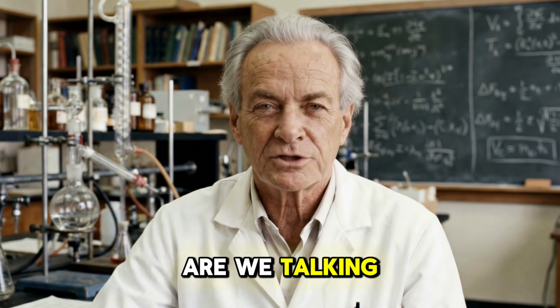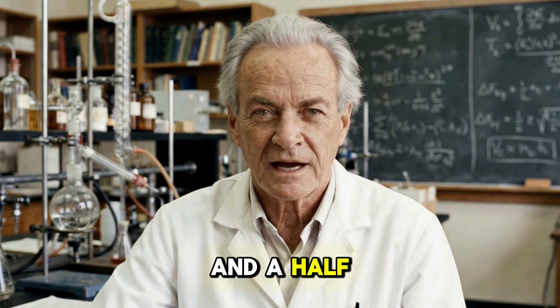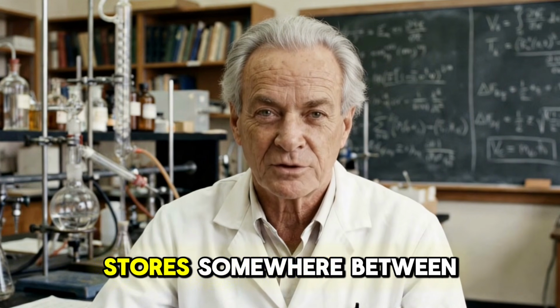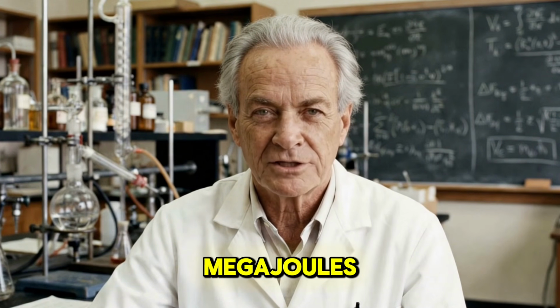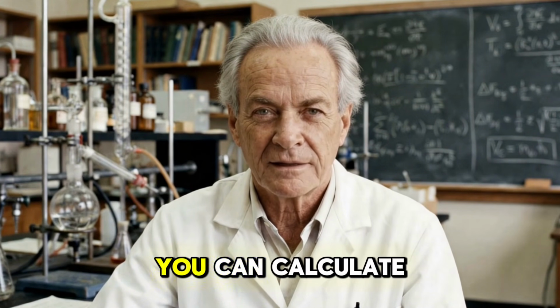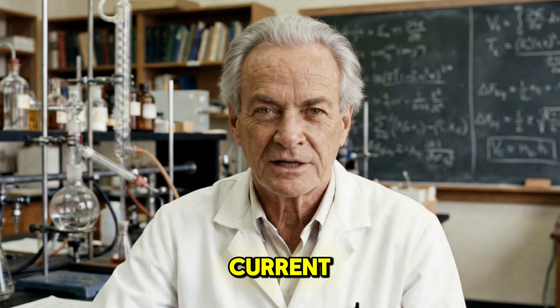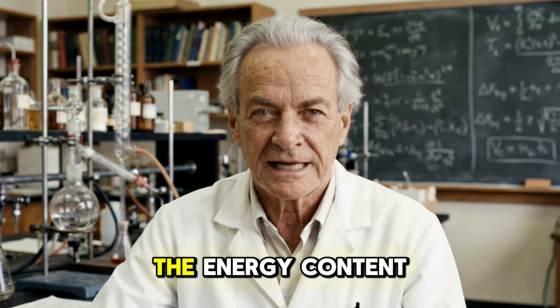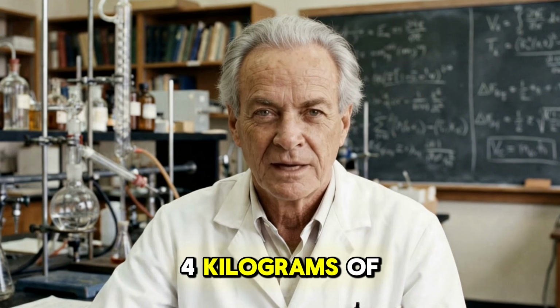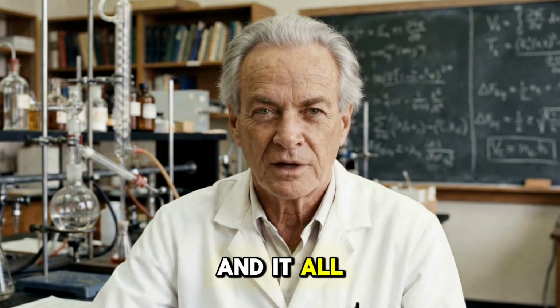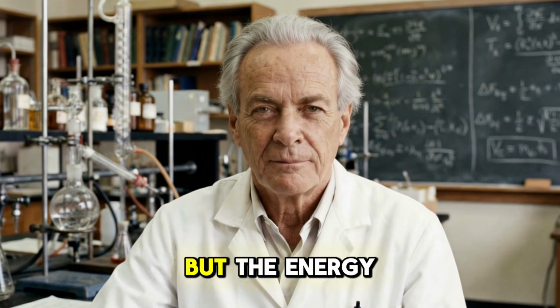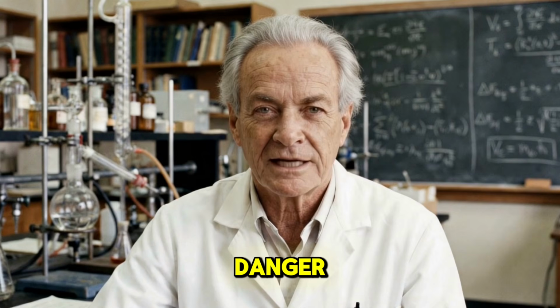How much energy are we talking about? A typical 1.5 Tesla clinical MRI stores somewhere between 5 and 15 megajoules in its magnetic field. You can calculate it from the inductance and the current. It comes out to roughly the energy content of 2 to 4 kilograms of TNT. And it all comes out in a matter of seconds. But the energy itself is not even the main danger.